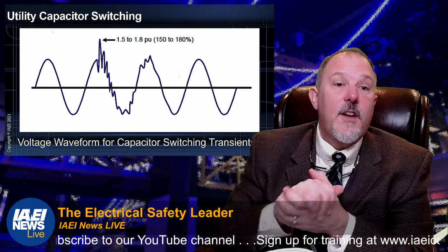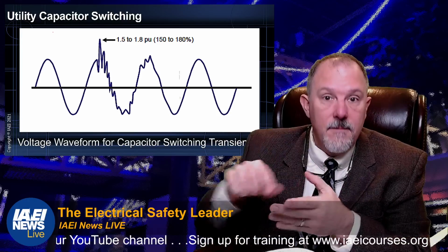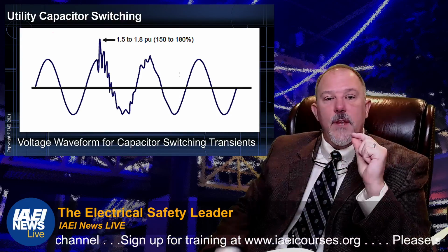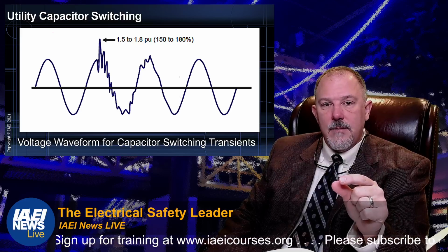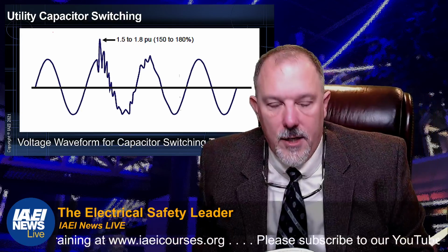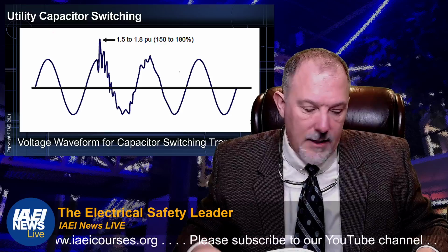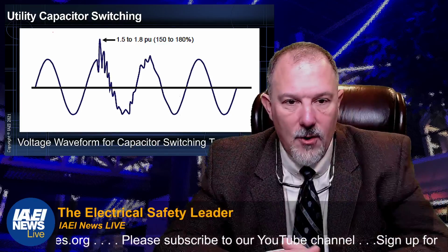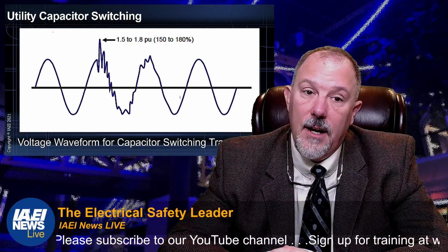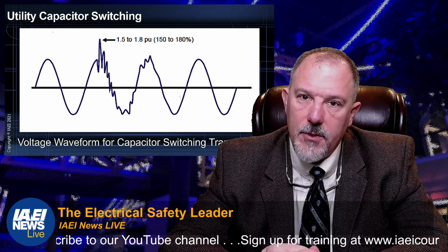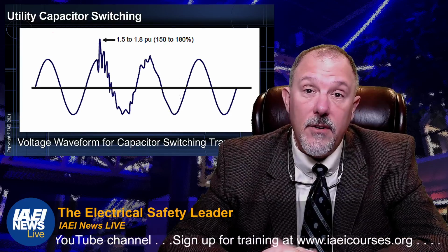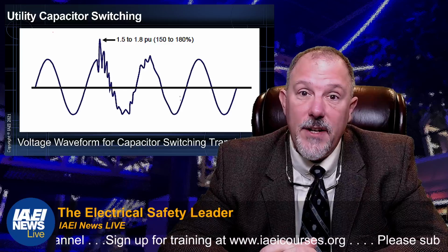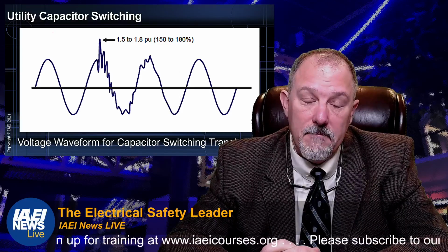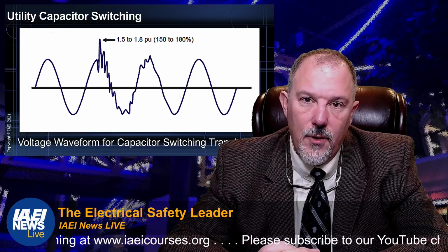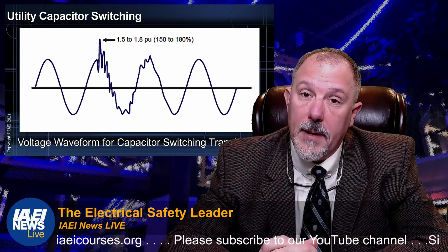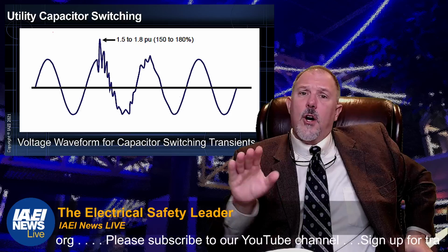Here's an example of a capacitor switch. We call it a ring wave, right? So that is a capacitor switching transient. I was called out a while ago to California. We had a facility. This is in the early days of arc fault circuit interrupters. I'm talking branch feeder AFCIs. And we had an issue where the circuit breaker was tripping in a complex.